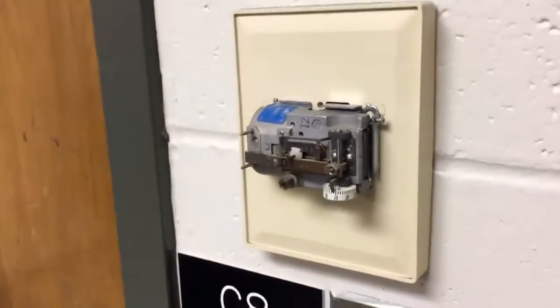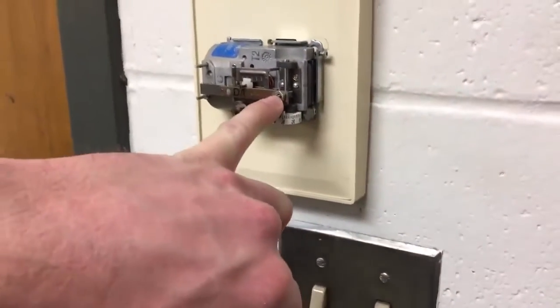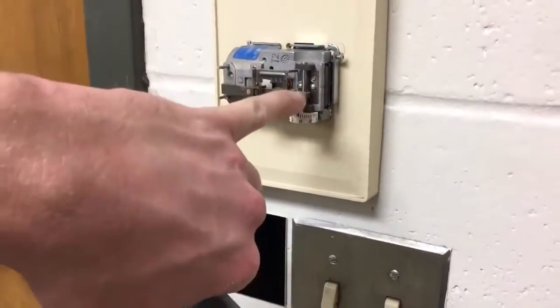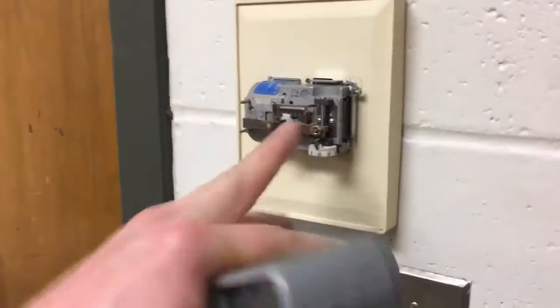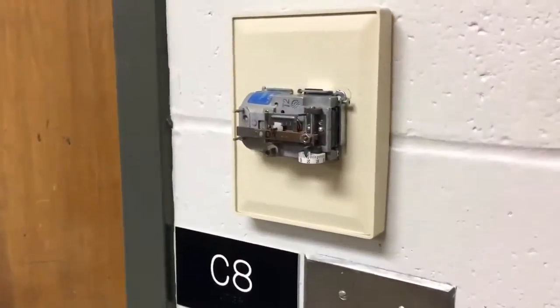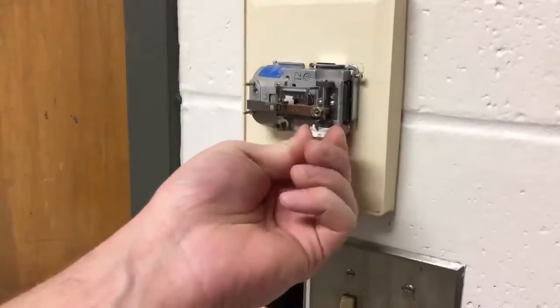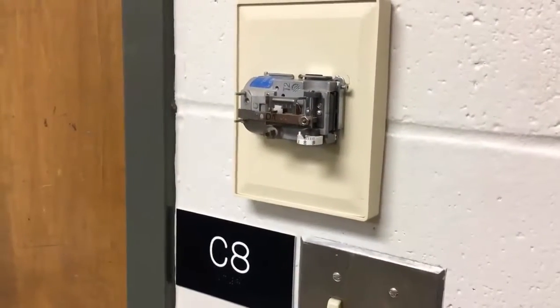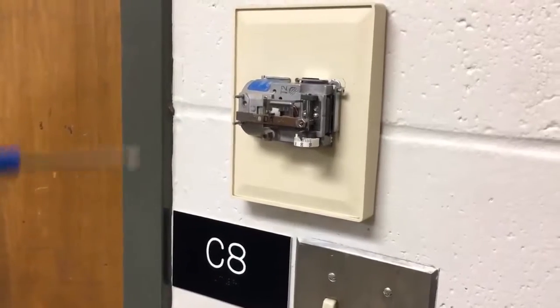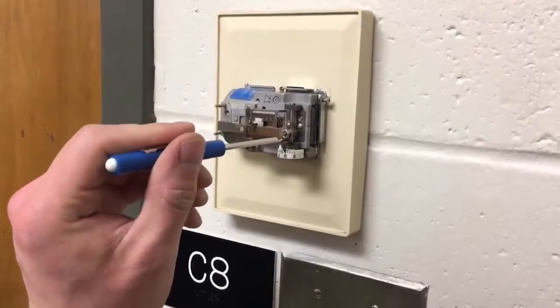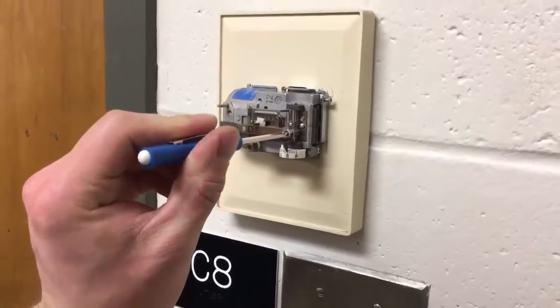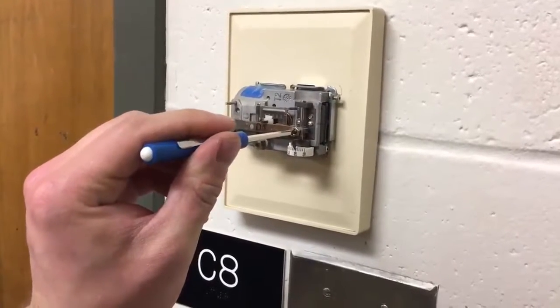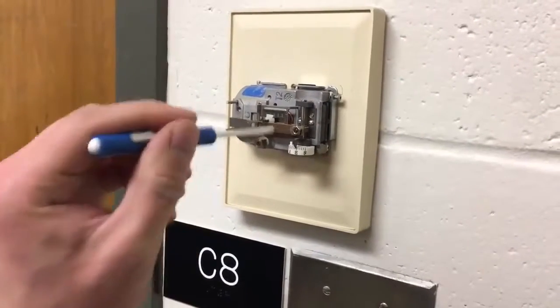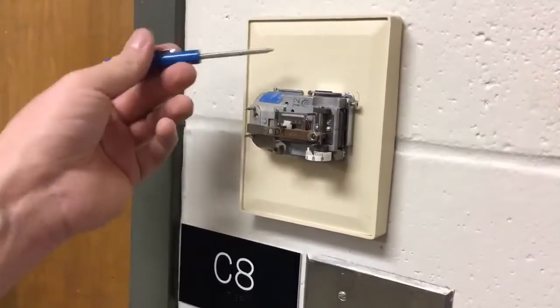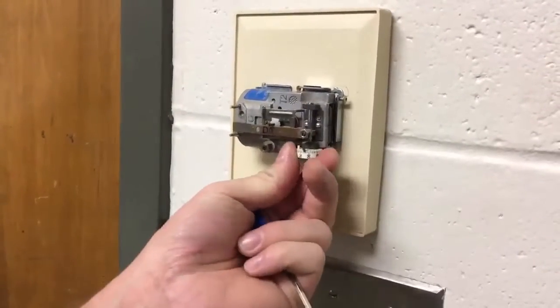The way to calibrate that is this set screw here. You turn it clockwise, you increase the temperature that it thinks it is, you turn it counterclockwise, you decrease. So since it's actually 80 degrees in here, if we set this to 80, you take a little flathead screwdriver and you can turn this until it pressurizes again. So there you hear it build pressure.